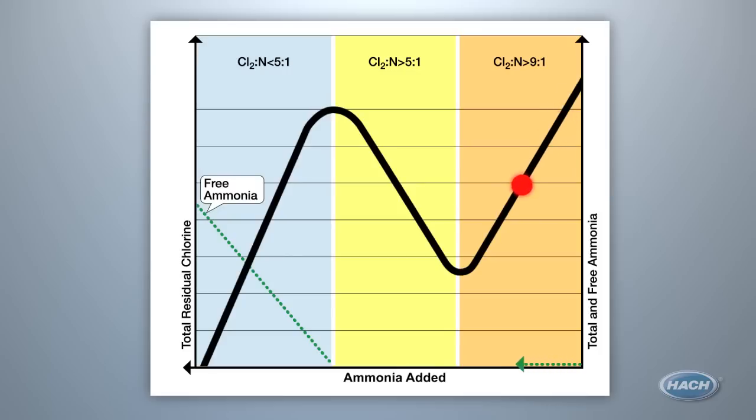Ammonia is added to the chlorinated water just prior to entrance into the distribution system. The dose is increased until a small trace of free ammonia is detected, ensuring you are in zone one and maximum monochloramine residual has been reached.